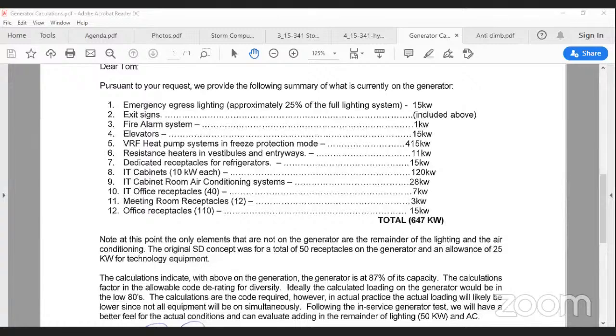When you refer to the vendor coming out to do the test on the generator, I was outside there with them on that day. They basically said that when they hooked the generator up to the town, we only had a 20 amp load on that particular generator, and they had to put 740 amps of load on it in order to put it under load.